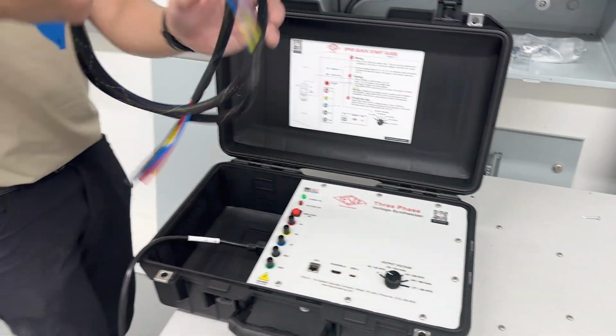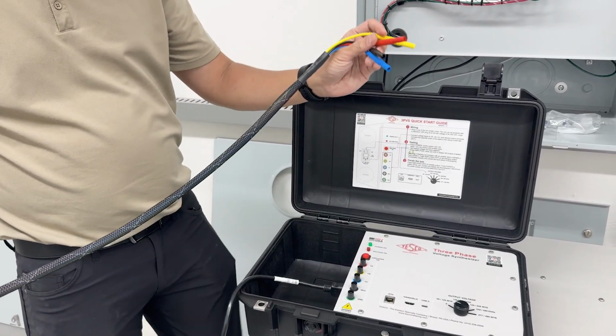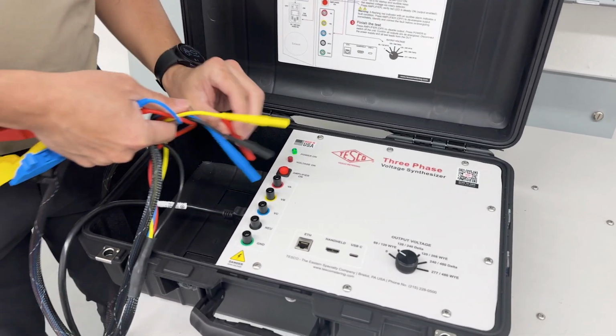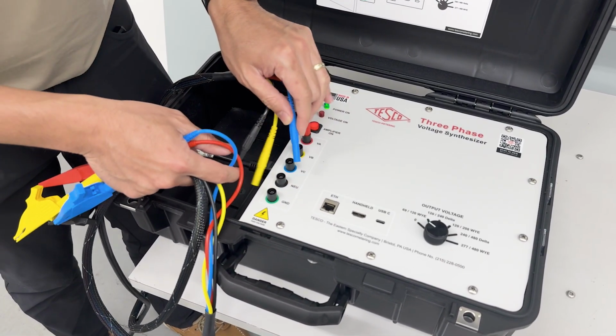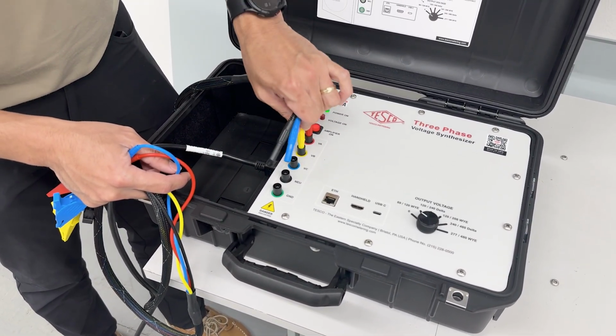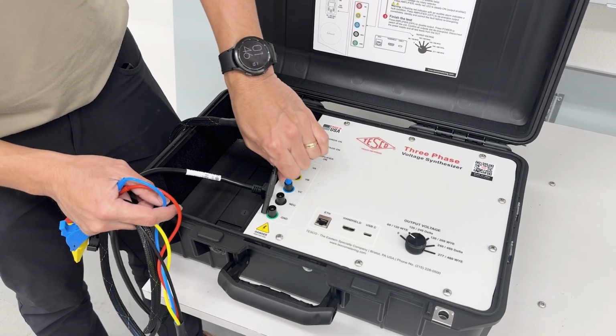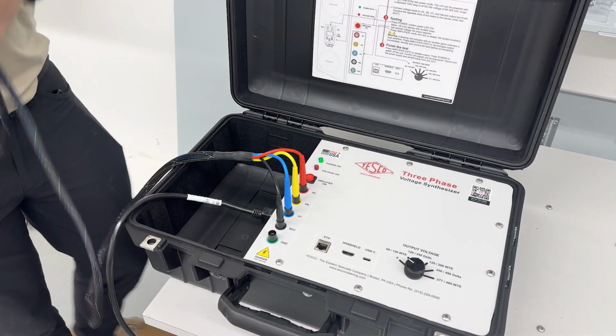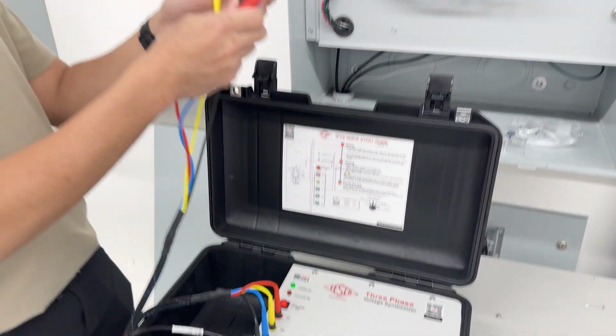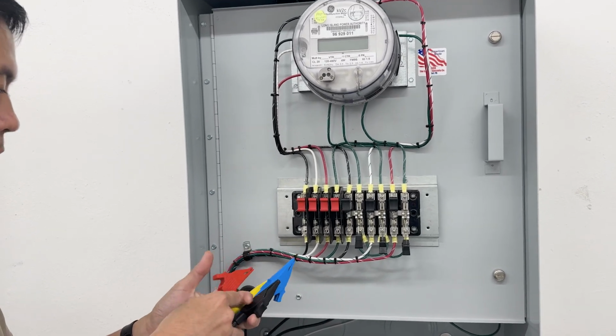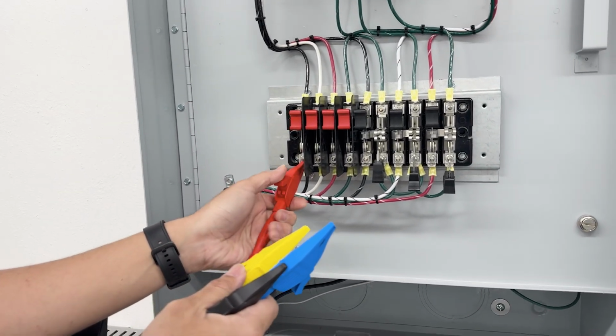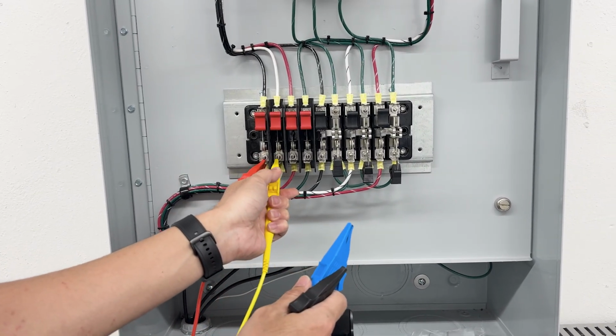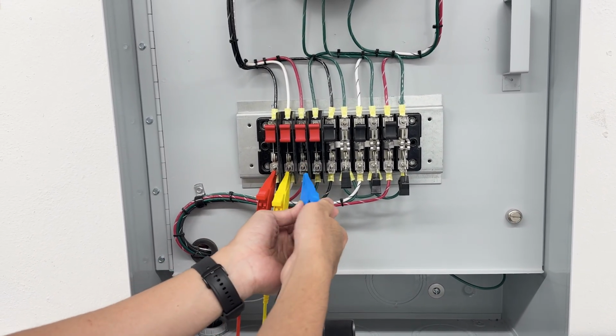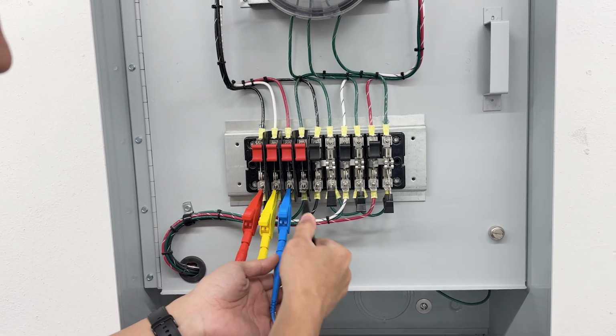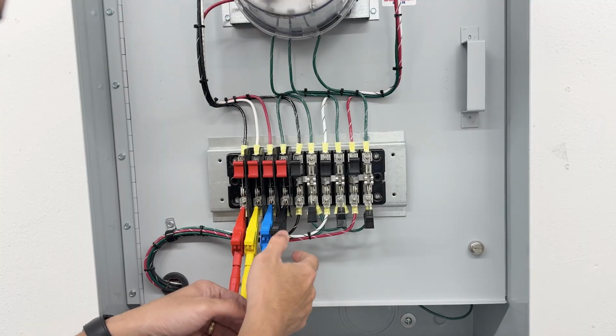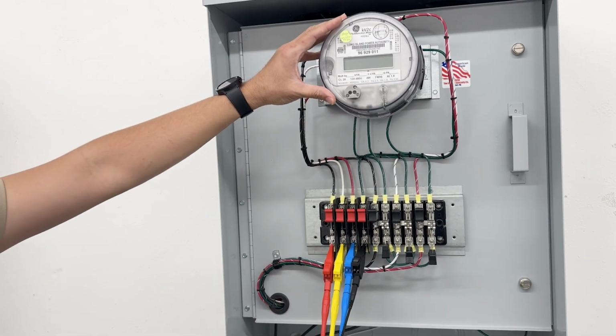So what we can do is grab our voltage cable set, just line up the color codes: red, yellow, blue, and black for the neutral. Okay, so I'm gonna connect these dolphin clips to the test switch. The same process. We're gonna line up the color codes. Red for phase A, yellow for phase B, blue for VC, and black for the neutral. Okay. Now it's connected. This is a 9S meter.